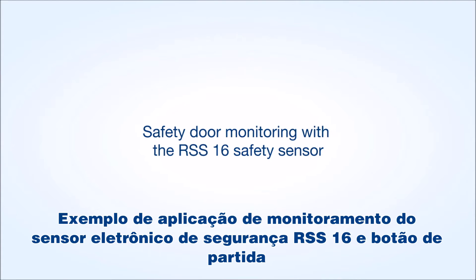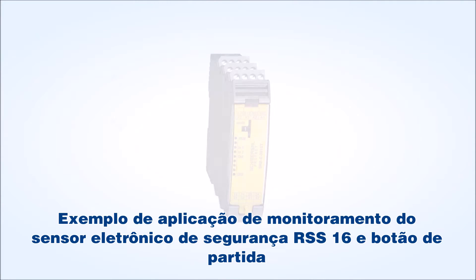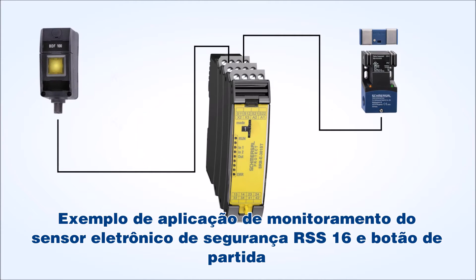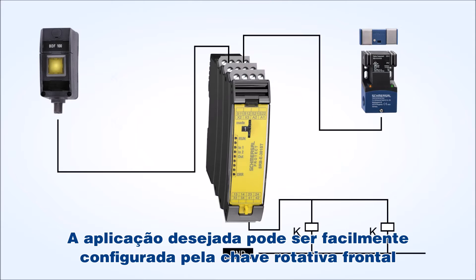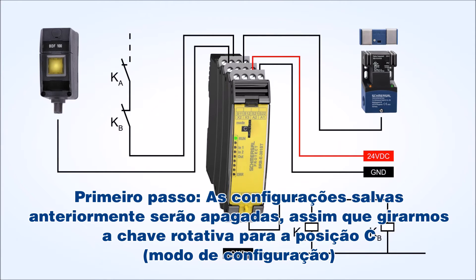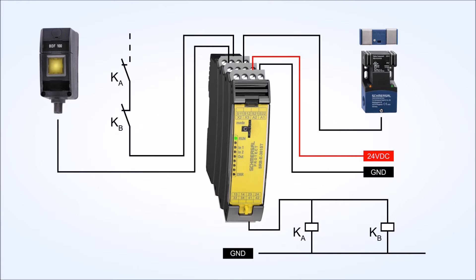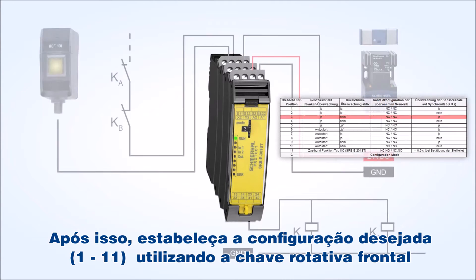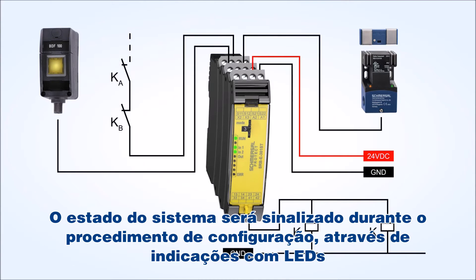Sample application of a safety door monitoring with the RSS 16 safety sensor from Schmersal and start button monitoring. The desired application can be simply configured by means of a rotary switch. Formerly saved configurations will be deleted first by turning the rotary switch to position C, configuration mode. Subsequently, set the desired configuration, 1 to 11, using the rotary switch. The system status will be signaled during the setup procedure by means of the LED indications.